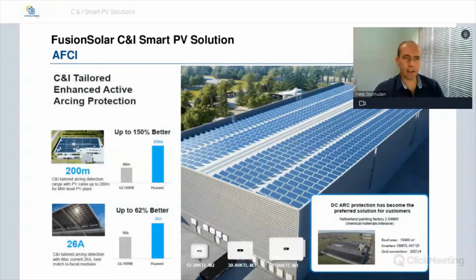Continuing on the AFCI, Huawei has tailored their AFCI for enhanced active arcing protection. If you look at the normal standard, you only need to detect up to a distance of 80 meters, but with Huawei you can detect AFCI up to 150% better than the standard, which is then 200 meters. Also, looking at the standards, you only need to detect up to 16 amp, but Huawei is already certified and tested at 26 amp, so it's 62% better than the standard.